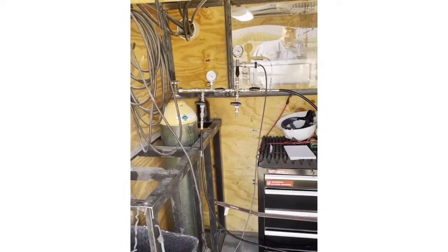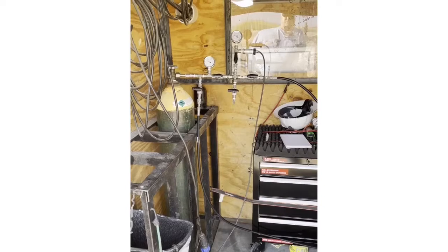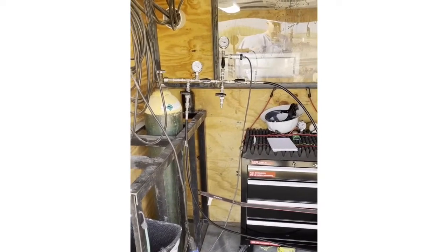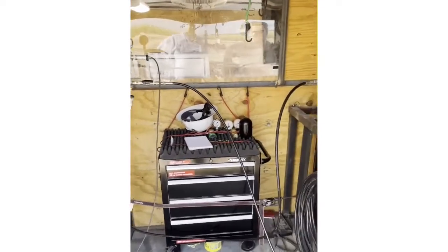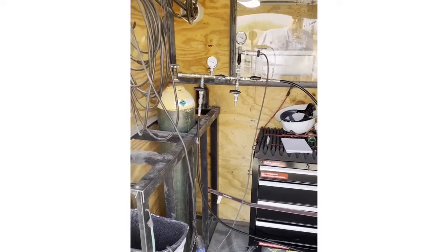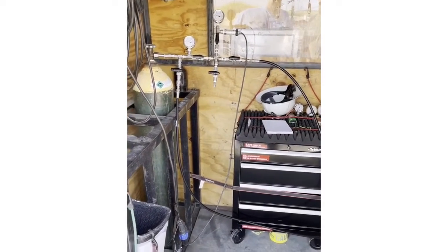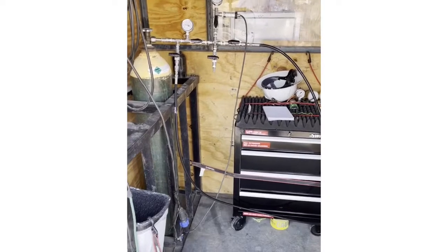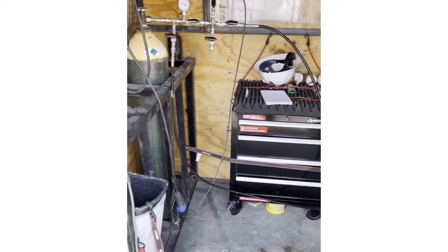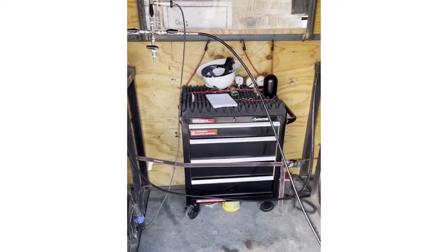So we're injecting liquid CO2 currently. We take a weight, and our goal is typically to inject about 25 pounds of liquid CO2, and we do it with weight on the bottles. Once we've achieved that, we'll stop the CO2 injection and start monitoring, watching for CO2 returns in case you had a leak right at surface or something that could come in right away. We start the test before we inject the CO2 to get our baseline, usually about 15 minutes of baseline, and then we'll inject the CO2. Now the CO2 is injecting, and we'll be able to start the monitoring test.